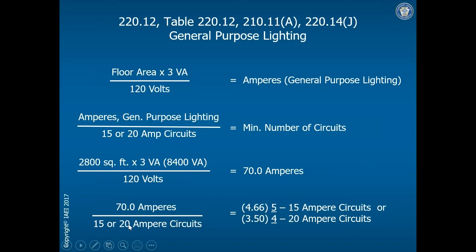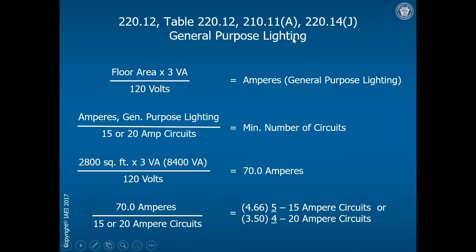That means at a very minimum, this 2,800 square foot house would need five 15-amp general lighting circuits. If using 12-gauge with 20-amp circuits, 20 goes into 70 three and a half times, so we'd need at least four 20-amp general lighting circuits. Importantly, per section 220.5, you cannot drop the decimal here — if the result is 4.16, you still round up and need a minimum of five 15-amp general lighting circuits to satisfy the general lighting load for this dwelling unit.